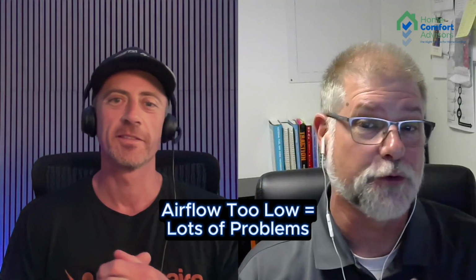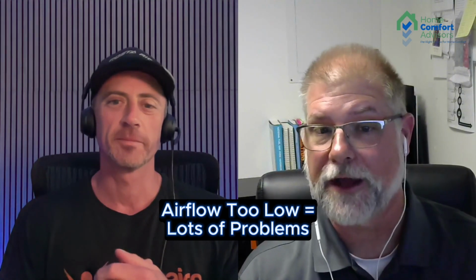But David, you told me to lower the airflow so that it helps remove moisture from the air. And now you're telling me that lower airflow is going to cause a problem. So let's talk about context. Airflow has to be within certain limits. If it's too low, then you can end up with all kinds of problems, like the indoor coil freezing. You can have a lot of problems. If the airflow is too high, then it's actually blowing the air past the coil so fast that it doesn't have a chance to remove the moisture.